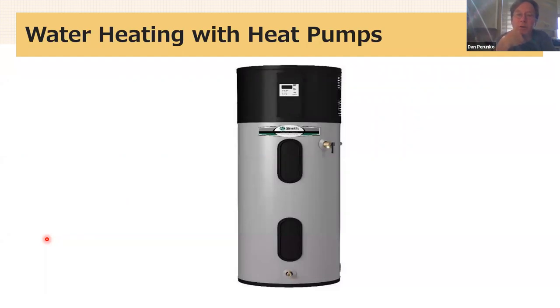This is a unitary heat pump water heater. So down here is the water, and then up here is the heat pump. And there's an element in the middle that is basically a refrigerant coil, right? So the high temperature vapor refrigerant is being pushed through a coil that's submerged in the liquid, and the liquid is cooling the vapor down to its condensing point. The vapor cools down, it condenses, it releases the heat. And I was thinking about condensing and what temperature that would be happening at. Since the water temperature is heated to around 130 degrees, maybe as much as 150 degrees, in these machines, they're set up so the condensing temperature of the vapor is probably around 150, 160 degrees Fahrenheit.